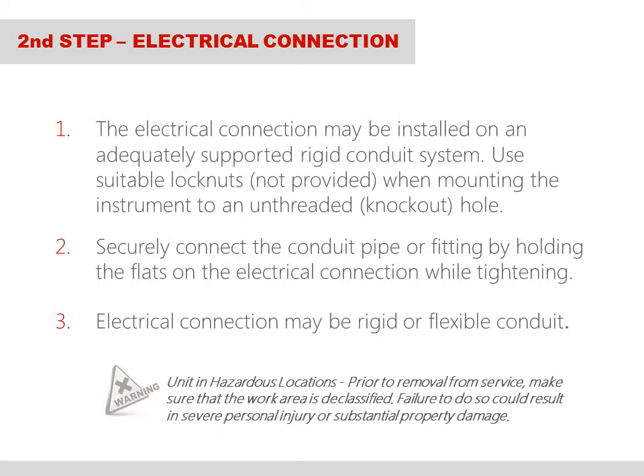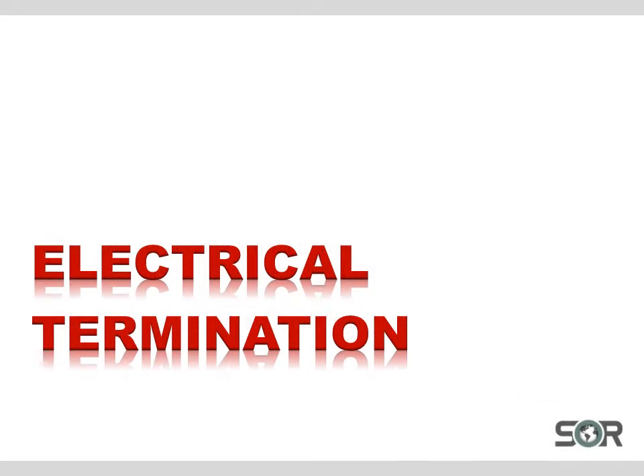SOR recommends using a 1 1/8 inch open-end wrench on the flats of the electrical connection when tightening the conduit pipe or fitting. The open-end wrench provides a counterforce to prevent the 815 from rotating when the conduit pipe or fitting is being securely connected. The 815 PT can be connected to rigid or flexible electrical conduit or mounted into an unthreaded knockout hole using an appropriate lock nut. Make sure that the conduit system used is adequately supported. Now that we've completed the installation of the 815 PT, it is time to wire the instrument for the desired output.